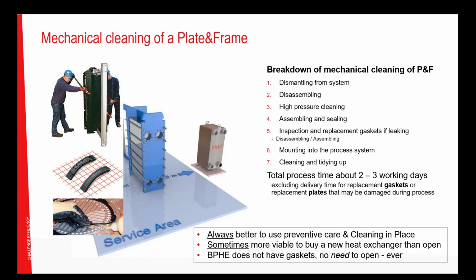From our point of view, we see the economic benefits of cleaning in place, first of all, avoiding fouling, number one. Number two, cleaning in place. These are the two most cost-effective ways of maintaining the economic benefit of a plate heat exchanger, a brazed plate heat exchanger being the more compact and cost-efficient of those.